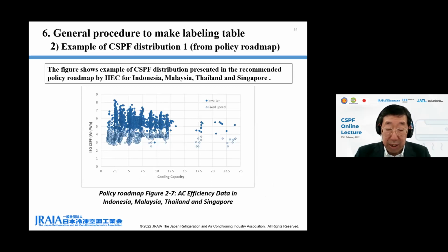The figure in this page shows an example of CSPF distribution in the recommended policy roadmap presented in the work package 2 by IIEC. The data show efficiencies converted to ISO T1 CSPF for products under 25 kilowatt cooling capacity sold in the markets in Indonesia, Malaysia, Thailand, and Singapore. Dark circles show inverter models and light circles show fixed speed models. As shown in the figure, CSPF of inverter models are distributed in the higher range from 4 to 8, and CSPF of fixed speed models are distributed in the lower range from 3 to 5. Next, please.